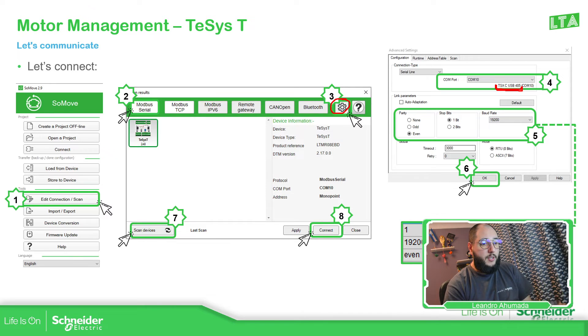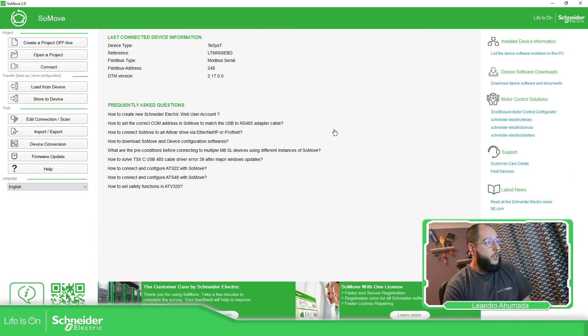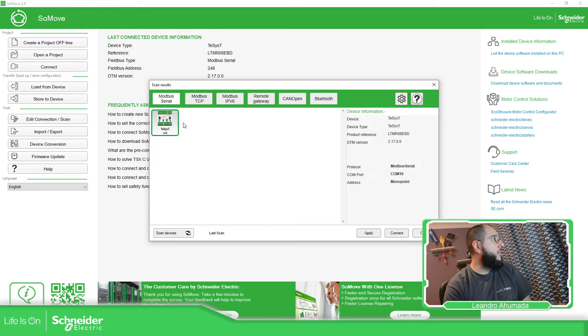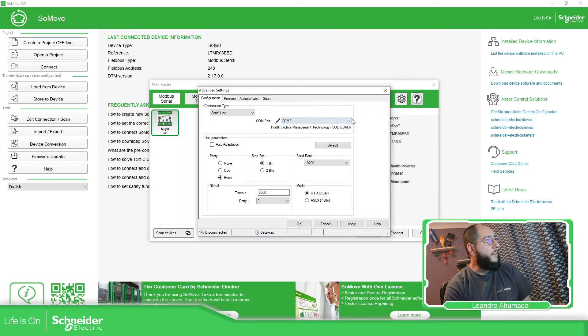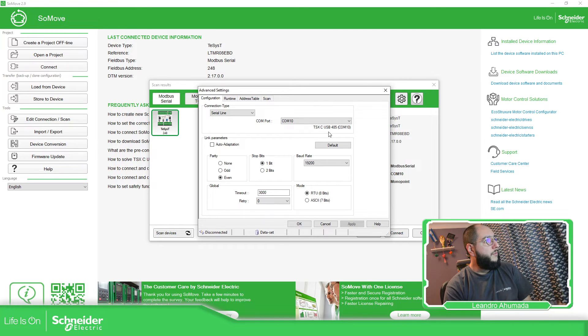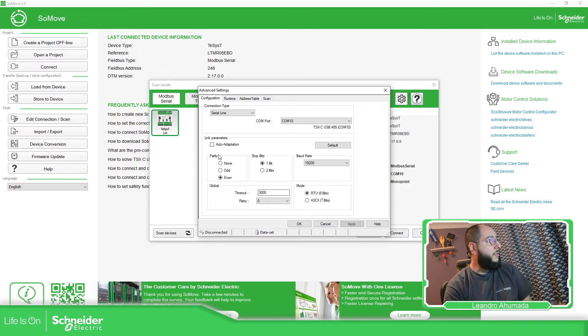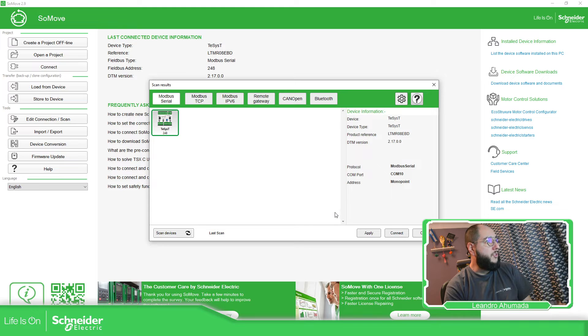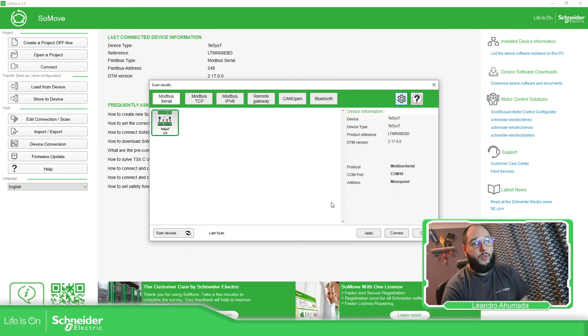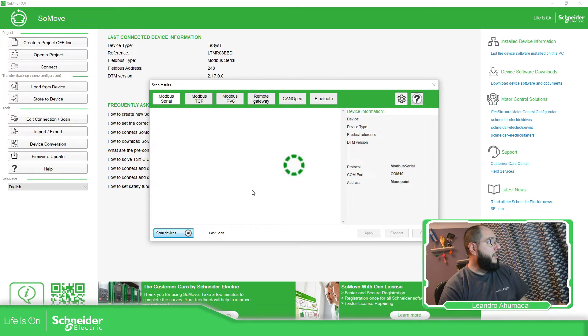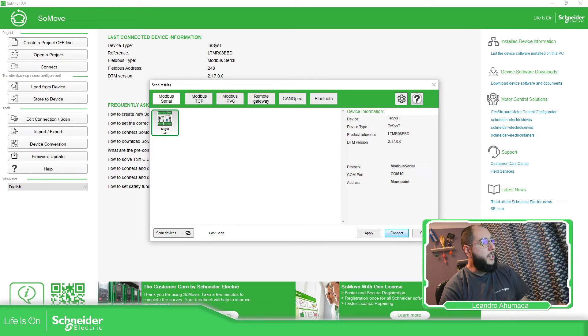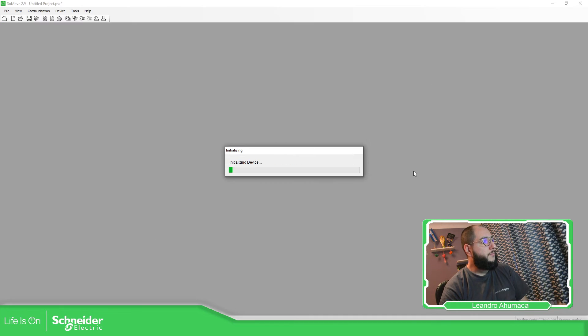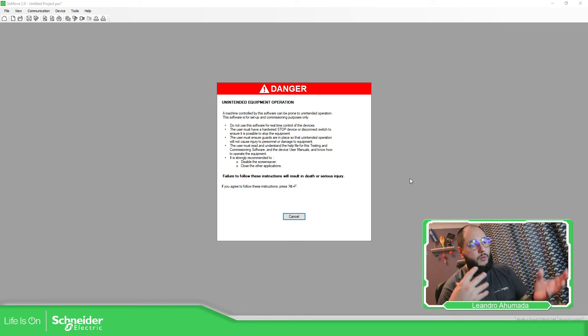Once you apply this scan for devices to see if you had a device on the network and then just connect. So let's try it. Here, edit connection. Here you can see that I have different things. And we need to select this one. This is mandatory. And then select the parity and stop bit and baud rate, which is the standard or the default for this device. Scan the network. Find the device. You can double click or just connect.